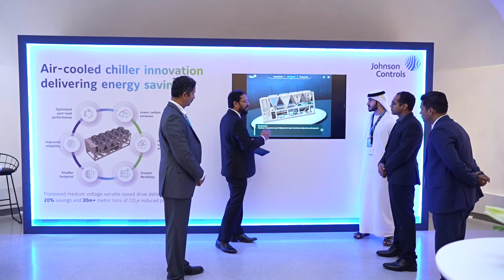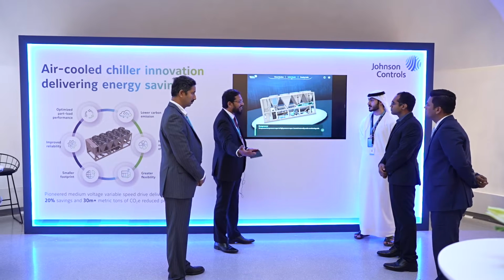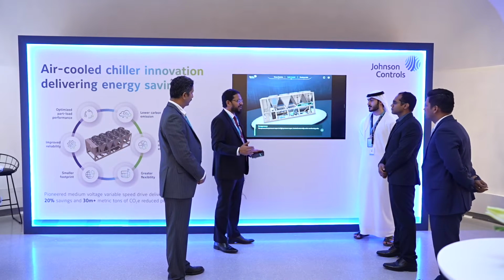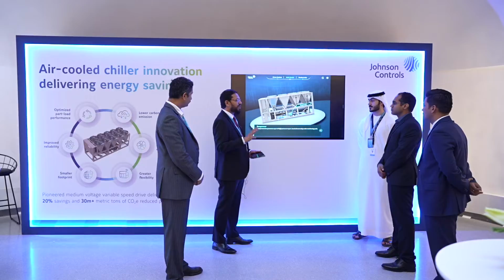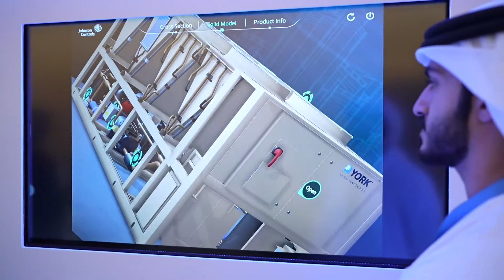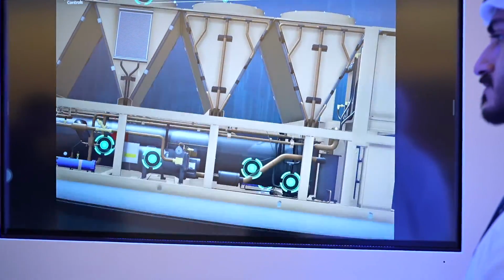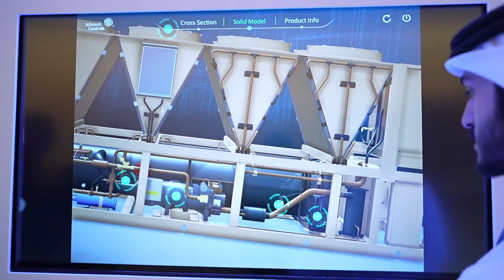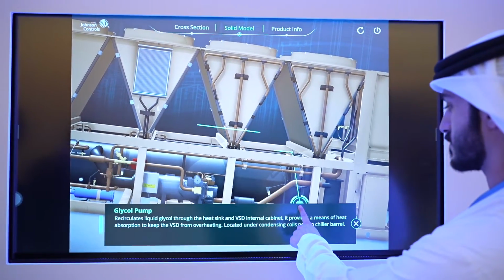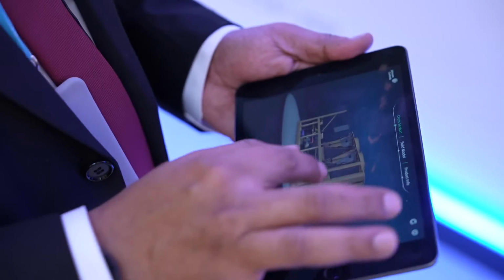That's exactly what applies over here. When the ambient is not that high, we reduce the speed of the compressors to make sure that it consumes only as much power as needed, which in turn can get you approximately 20% energy saving on your electricity bill, compared to the typical air-cooled chillers we conventionally have.